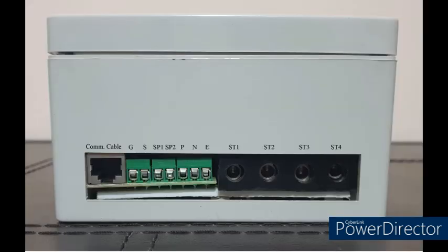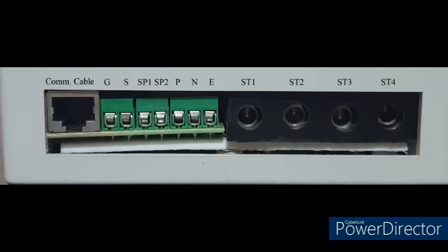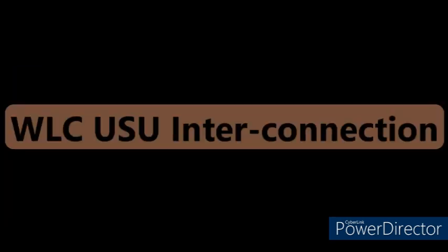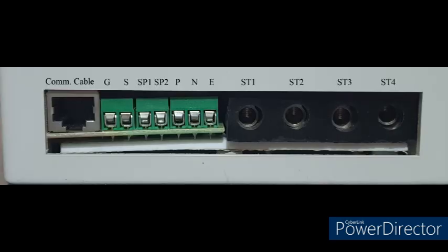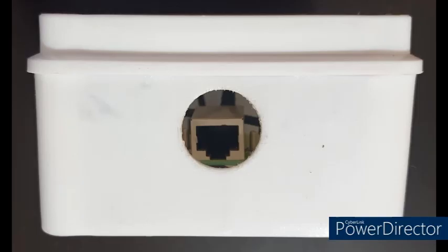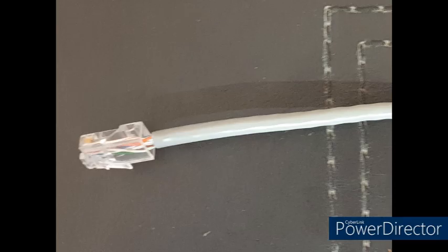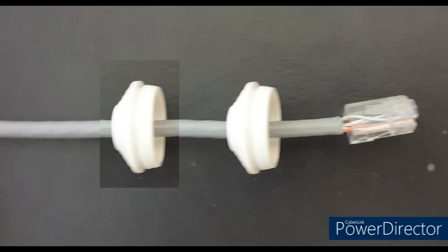WLC and power cord interconnection. Phase, neutral and earth of the power cord are respectively connected to P, N, and E terminals of WLC. Tighten the connection properly and then lightly pull it to check if it is properly fixed. WLC and USU interconnection. USU and WLC are connected via the sensor interconnection Cat6 cable with RJ45 connectors at both ends, as shown. Do not forget to put both rubber grommets at the USU end.